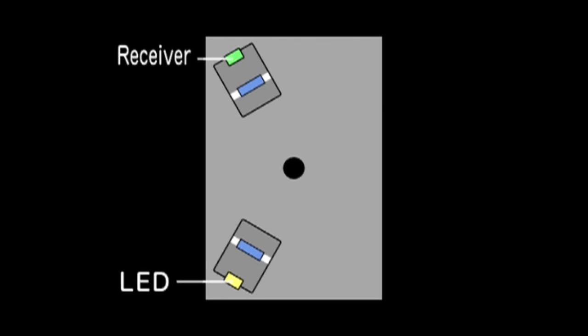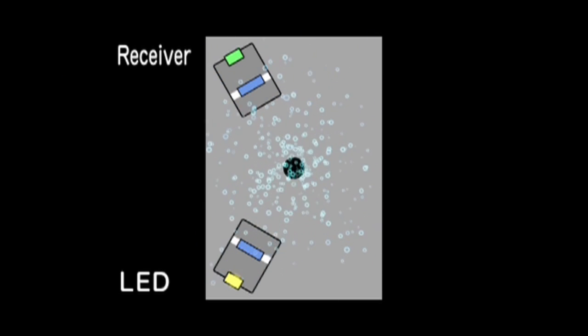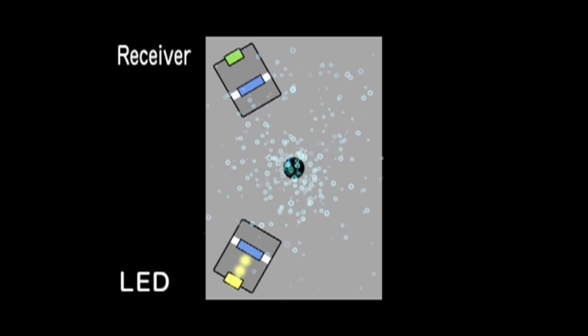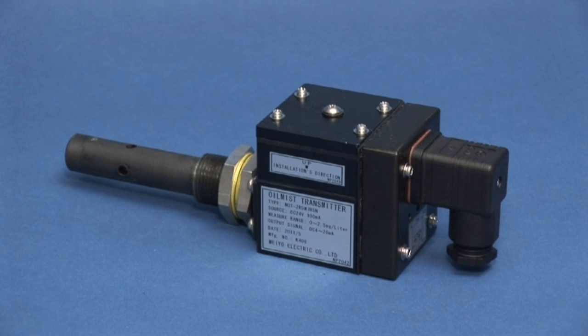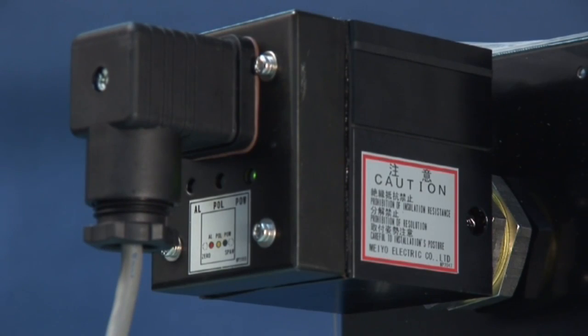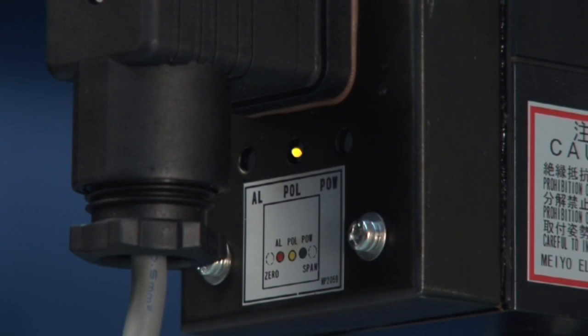The oil mist density detection is performed by the optical dispersion system using infrared rays. The pulse drive system is adopted as the mist detection part. It is highly sensitive and provides a high-speed response. The mist detection part of the oil mist transmitter is protected by an oleophobic cover for preventative measures against pollution. In addition, a warning is displayed in the event of pollution of optic parts or fan abnormality.